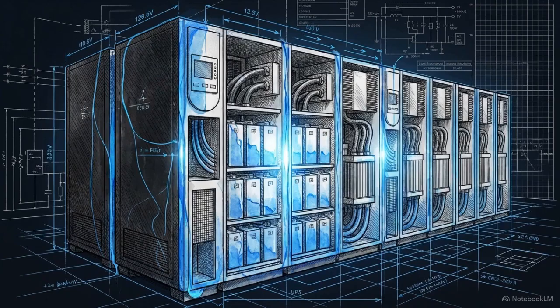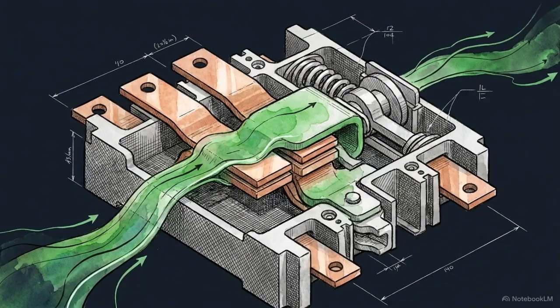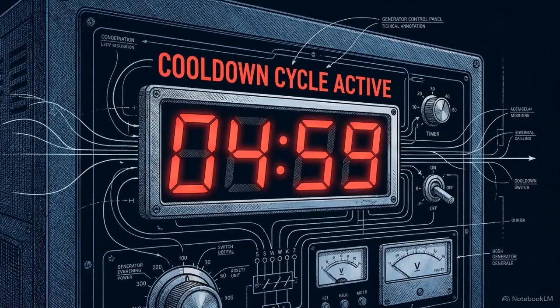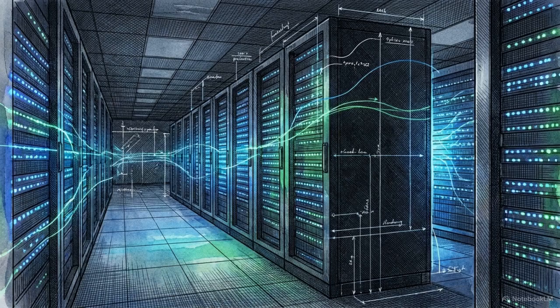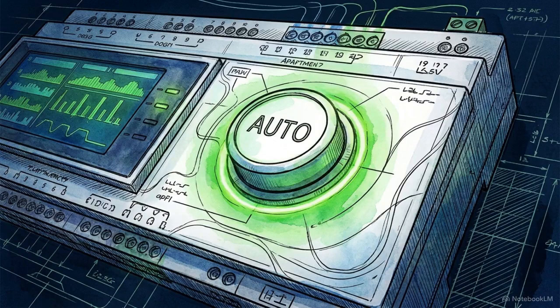The UPS steps in, discharging its batteries to bridge the gap and maintain the critical load. Finally, Q1 closes, restoring the utility grid to the facility. With the load securely back on source 1, you initiate the approved generator cooldown procedure. Every controlled transfer relies entirely on the health of the UPS batteries to protect the servers from the harsh reality of the break-before-make sequence. For standard, unattended operation, the ATS remains in auto mode.